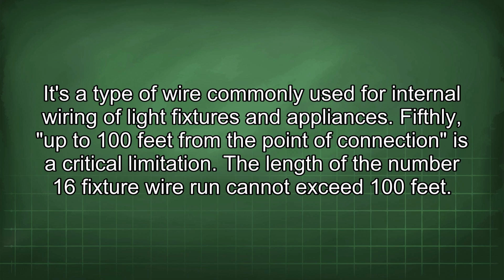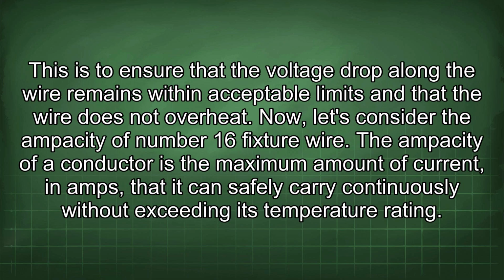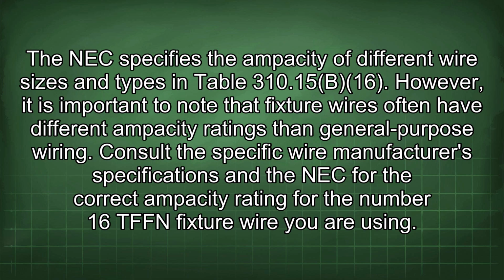Fifthly, up to 100 feet from the point of connection is a critical limitation. The length of the number 16 fixture wire run cannot exceed 100 feet. This is to ensure that the voltage drop along the wire remains within acceptable limits and that the wire does not overheat. Now, let's consider the ampacity of number 16 fixture wire. The ampacity of a conductor is the maximum amount of current, in amps, that it can safely carry continuously without exceeding its temperature rating.